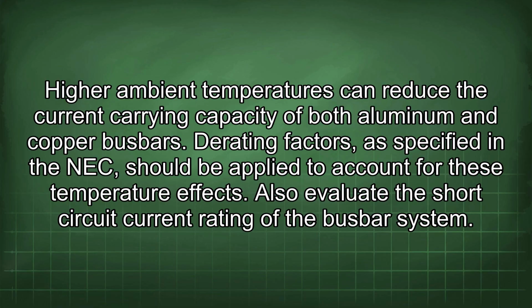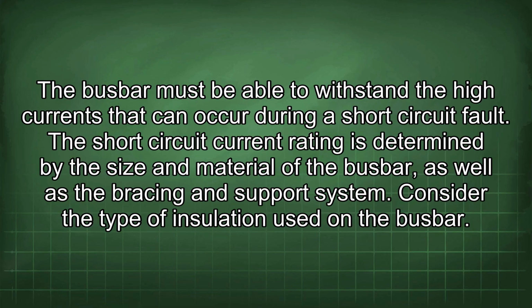Also evaluate the short-circuit current rating of the busbar system. The busbar must be able to withstand the high currents that can occur during a short-circuit fault. The short-circuit current rating is determined by the size and material of the busbar, as well as the bracing and support system. Consider the type of insulation used on the busbar.